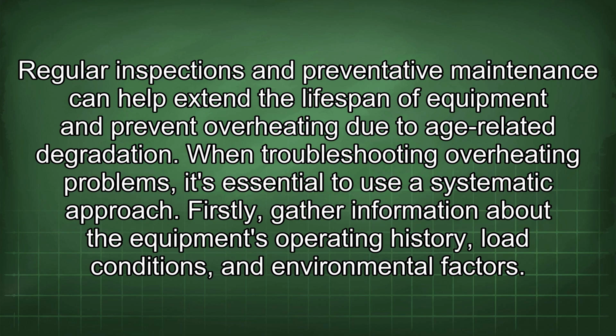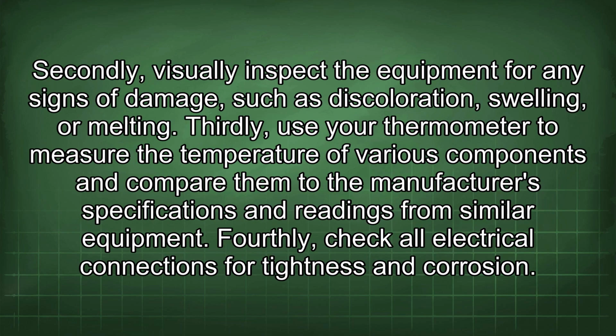When troubleshooting overheating problems, it's essential to use a systematic approach. Firstly, gather information about the equipment's operating history, load conditions, and environmental factors. Secondly, visually inspect the equipment for any signs of damage, such as discoloration, swelling, or melting. Thirdly, use your thermometer to measure the temperature of various components and compare them to the manufacturer's specifications and readings from similar equipment.